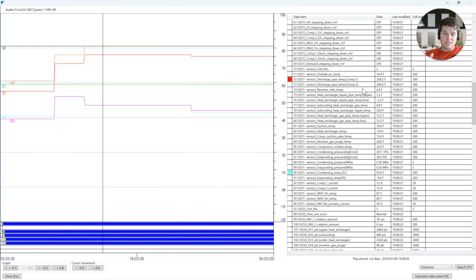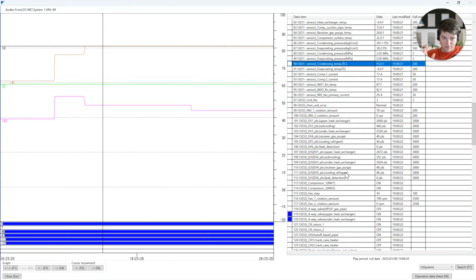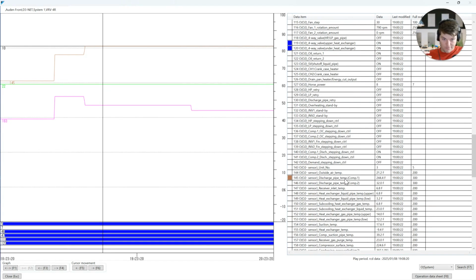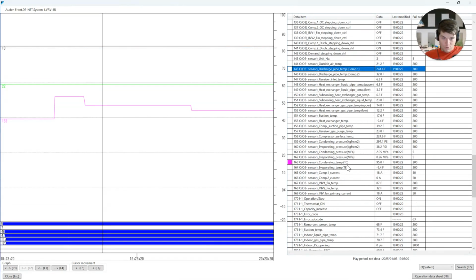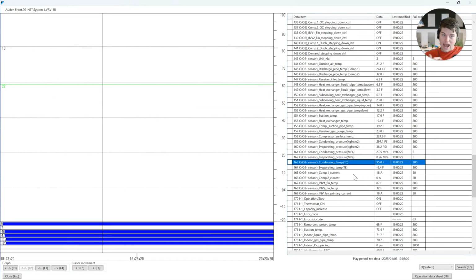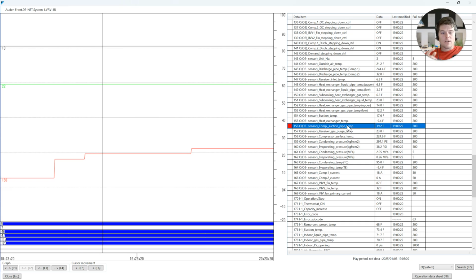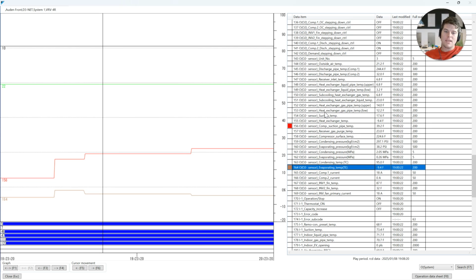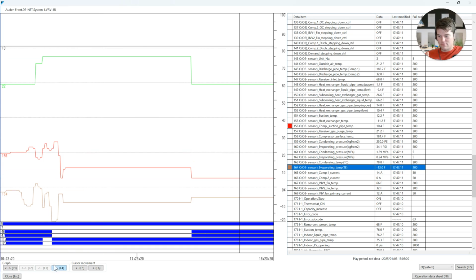Let's look at suction superheat. Now remember, we're not going to get crazy and populate a bunch of stuff on the screen because that's just going to get us confused, right? We're technicians, we're easily confused. I'll own it. I'm easily confused, even though I've been doing this for a long time. We're going to take our suction pipe temperature and I'm going to look at my TE. What do we need to know for superheat? I need saturation temperature and I need temperature of the pipe.